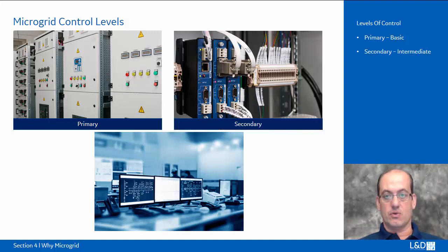A second level of control is when you bring in the automated control. You have a controller in place, like the DMC 490, and it communicates to the local DERs and controls them, making sure that they are providing not only power when there isn't power from the main grid, but providing economical setups where you might want to discharge your battery when the grid provides power at a more expensive tariff, and it makes more economical sense to use a local battery storage system.